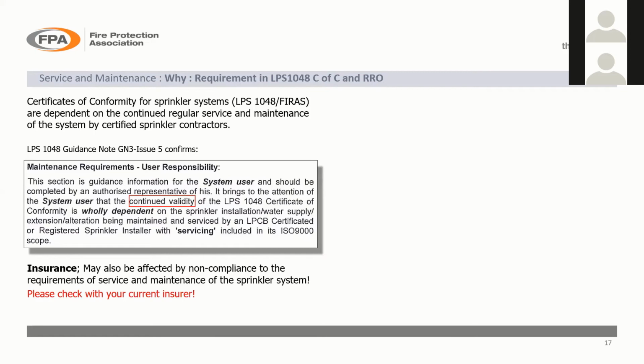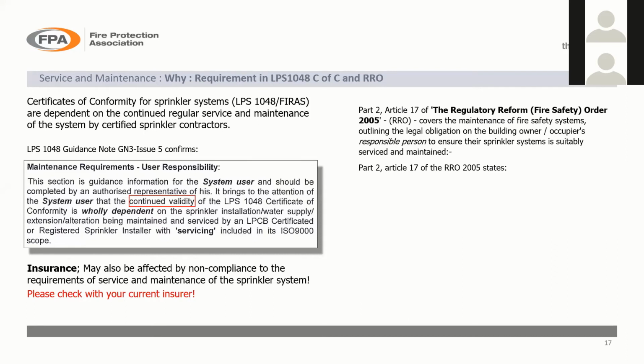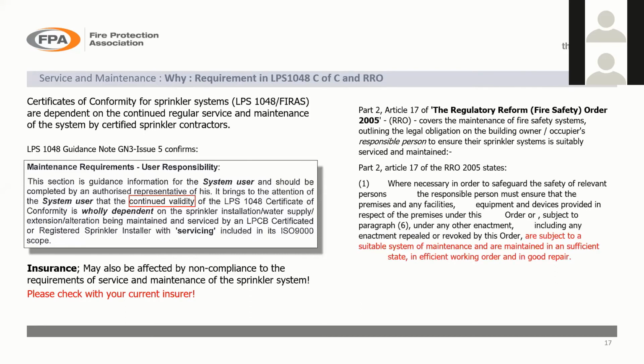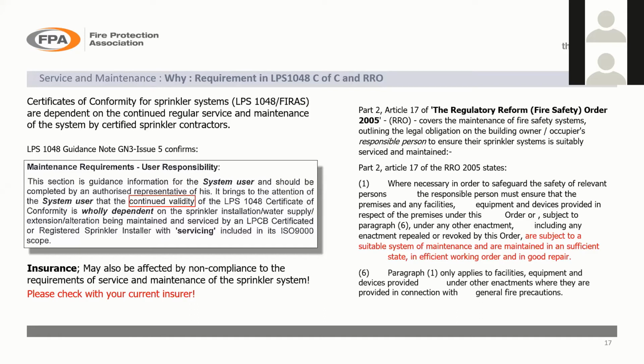Also, it's an insurance requirement. It's a good chance that if you don't maintain your system, then you're probably not going to be covered from an insurance point of view. That's something that you would need to check with your insurer. And it's also part of the legal requirement in the Regulatory Reform Fire Safety Order of 2005. I'm just skipping through this now, but obviously in there it does say that fire systems should be subject to a suitable system of maintenance and maintained in an efficient state, in efficient working order and in good repair.